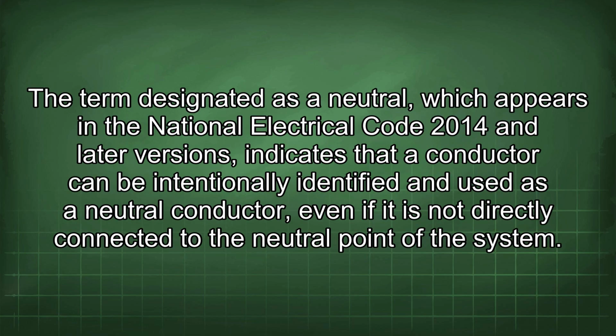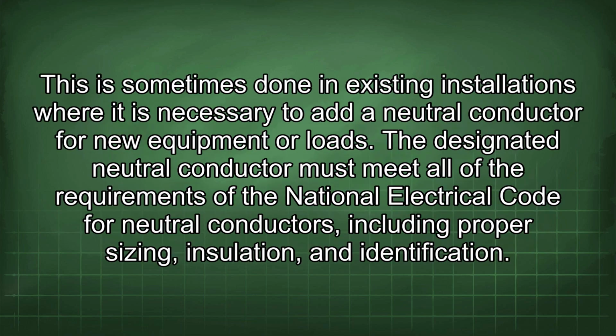The term designated as a neutral, which appears in the National Electrical Code 2014 and later versions, indicates that a conductor can be intentionally identified and used as a neutral conductor, even if it is not directly connected to the neutral point of the system. This is sometimes done in existing installations where it is necessary to add a neutral conductor for new equipment or loads. The designated neutral conductor must meet all of the requirements of the National Electrical Code for neutral conductors, including proper sizing, insulation, and identification.